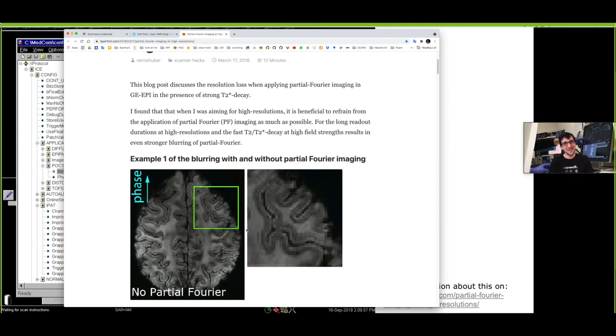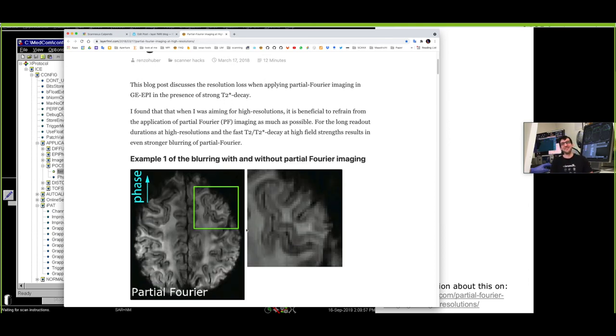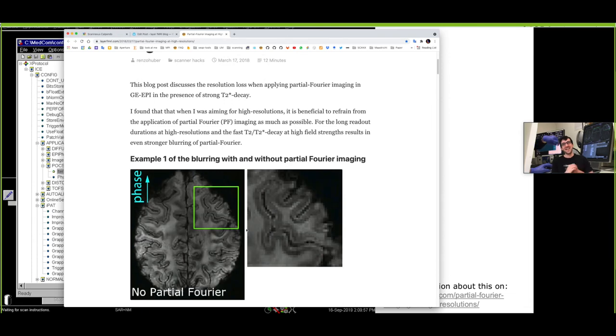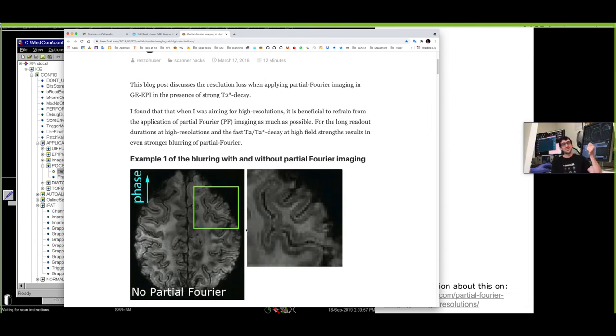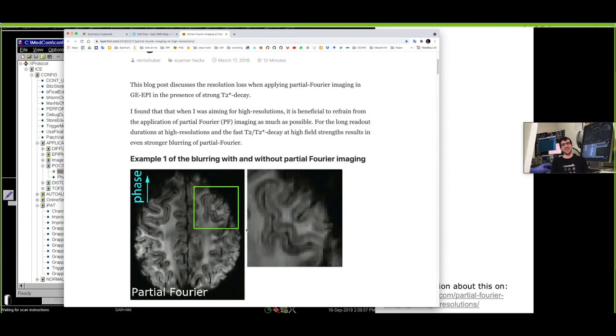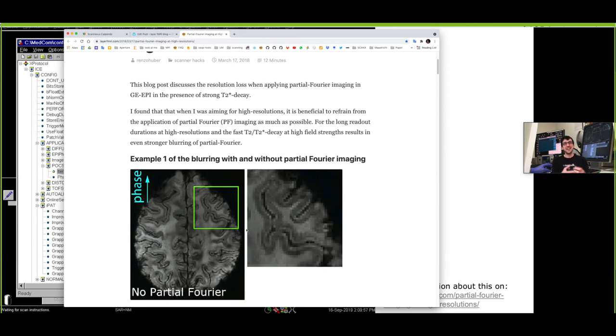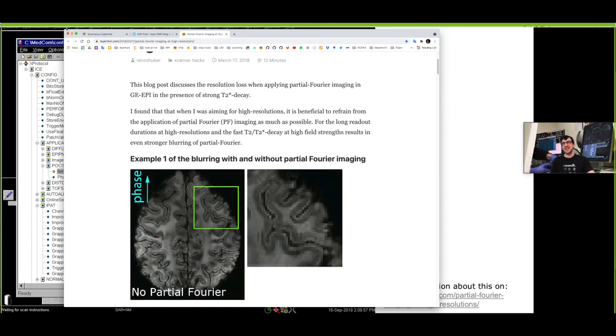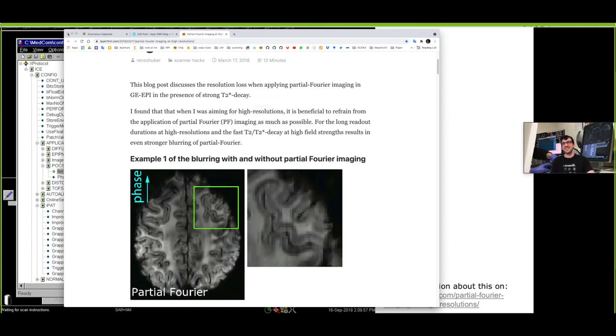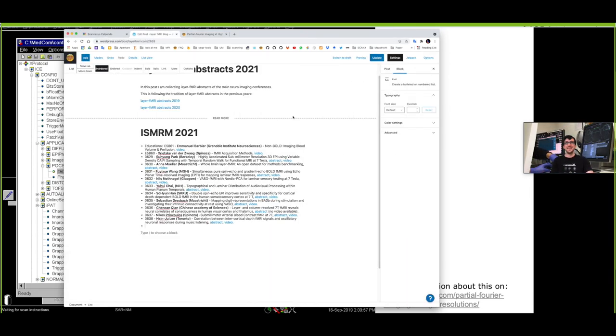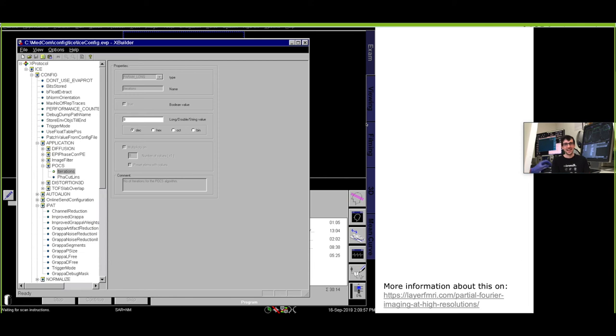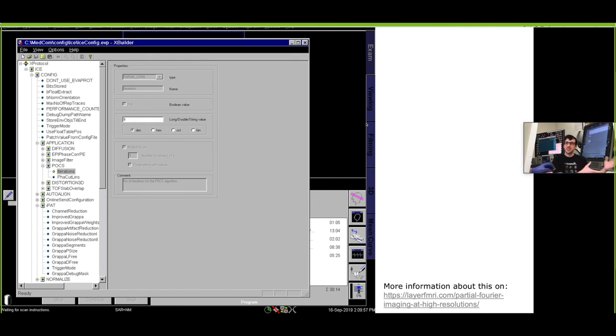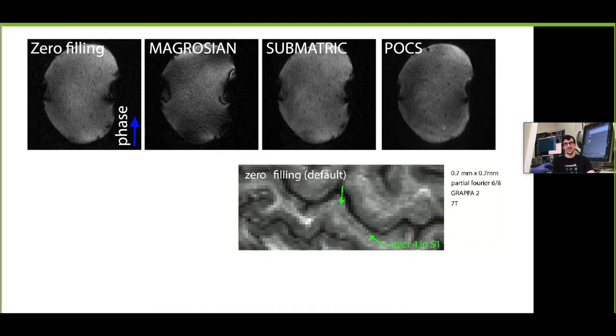I urge you, I challenge you for your next experiments that you're doing just switch off partial Fourier and see what it does with your data to get a feeling of how big the blurring actually is. I think a wise man once said that partial Fourier imaging is somewhat like taking heroin. You know it's bad for you but then you sit there and you think you need it and you promise yourself yeah just the one. I think very often it just comes down to the question: do we want to have a blurry signal with partial Fourier or do we want to have a super noisy signal, basically having no signal but then having a sharp no signal? Usually I use partial Fourier but you need to know what it does with your data.